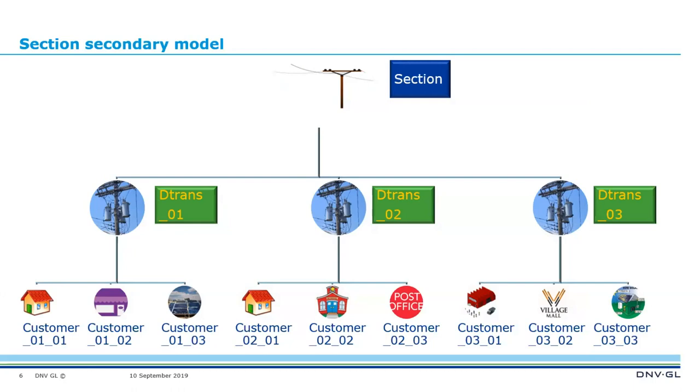And certainly in the early days of secondary modelling, people were looking towards having a customer instance for every customer on a distribution transformer, which really, if you start to combine that also with time series analysis, that is big data. And what we want to do is to balance the granularity of the data with the processing time to make sure that you have models that will deliver you results in a timely fashion, rather than have to wait days to get results, particularly on a large network.